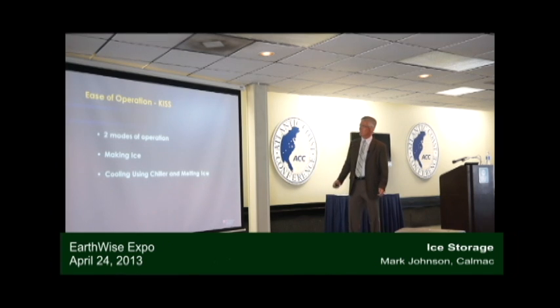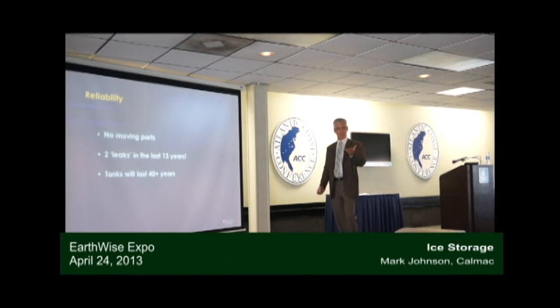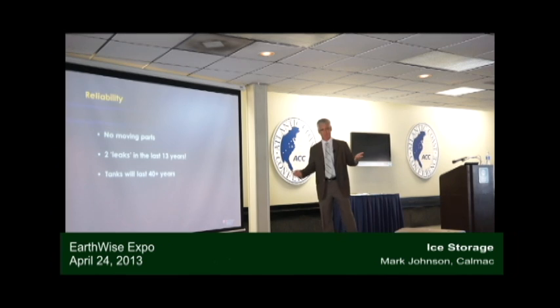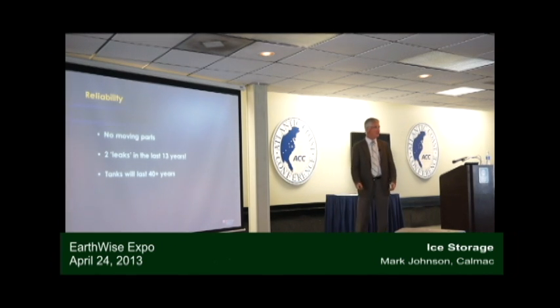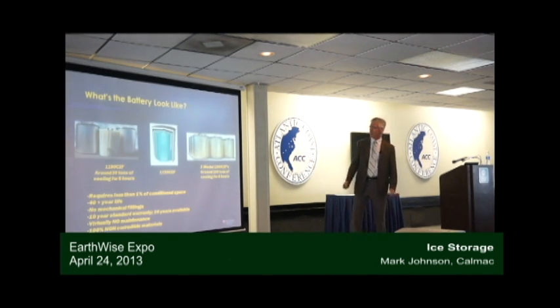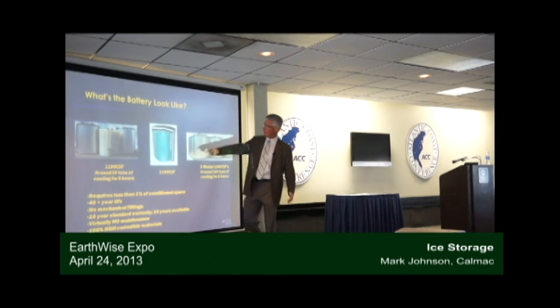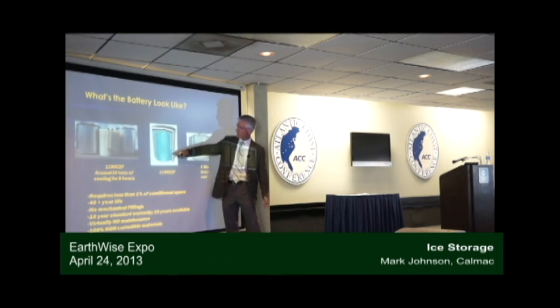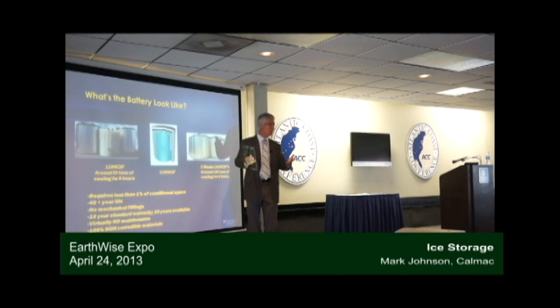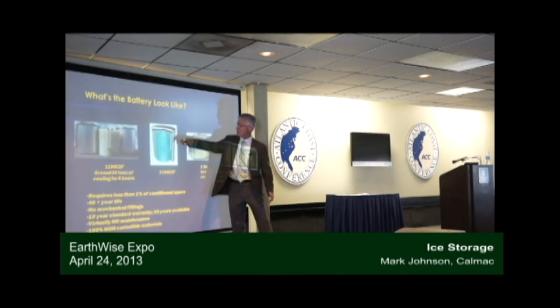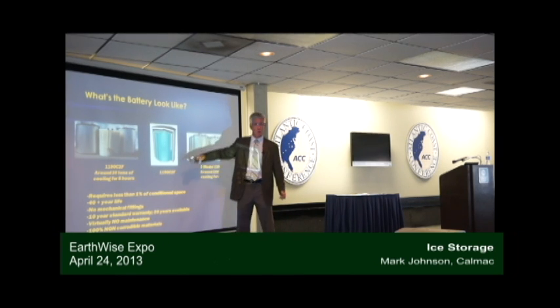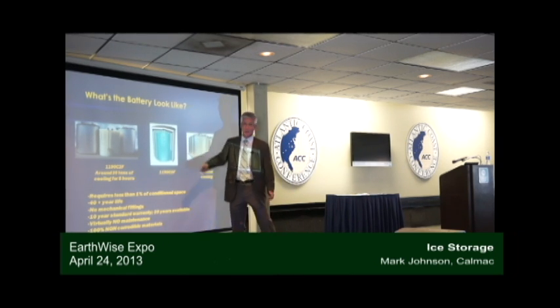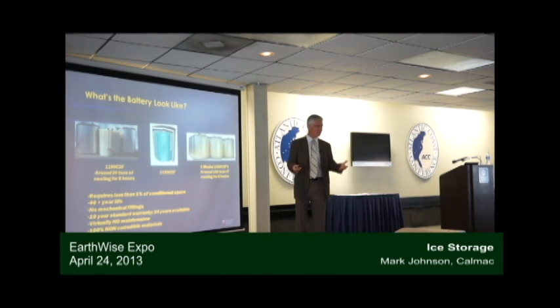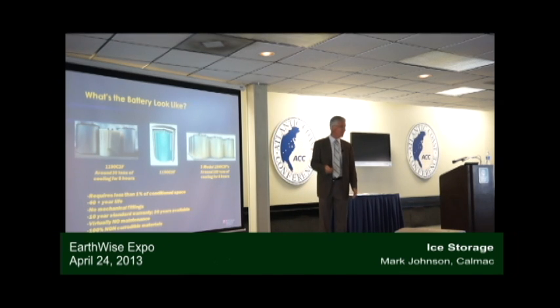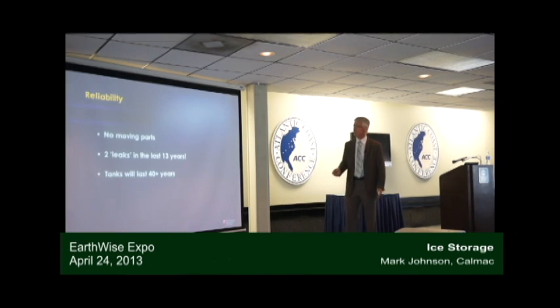Reliability, pretty good. We had a problem on a job here. We fixed it, right? We had a little leak. We fixed it. What do you do when you have a leak? In our systems, you have 56 circuits that you're building ice on. If you have a leak in one of these tubes, you simply plug that tube here at the header, and you've lost 1/56th of the capacity of your tank. That's about it.